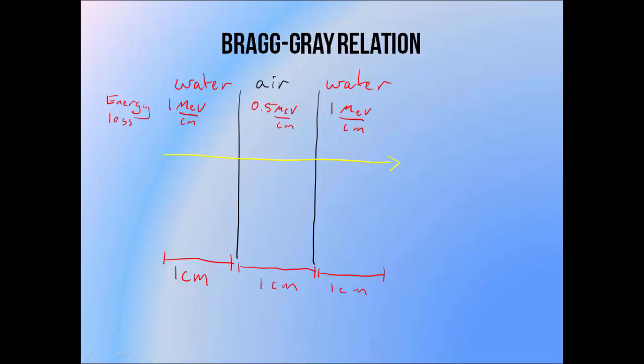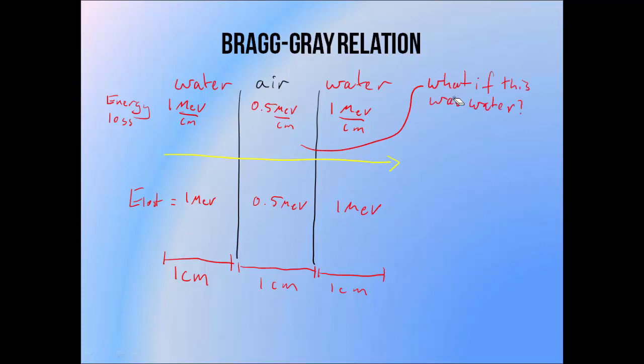An electron that travels 1 centimetre through the water above the chamber, and loses energy at a rate of 1 MeV per centimetre, will lose 1 MeV. An electron travelling 1 centimetre through the chamber, that loses energy at a rate of 0.5 MeV per centimetre, will lose 0.5 MeV. And it will lose another MeV in the water on the other side of the chamber. The Bragg-Gray theory uses this information to answer the question: what if the region of air inside the ion chamber was made of water instead? Well, we know the rate of energy lost per centimetre in water is 1 MeV per centimetre, so the electron would lose twice as much energy as it travelled that centimetre through the ion chamber. And the amount of energy deposited would be 1 MeV instead of 0.5 MeV. This is essentially all the Bragg-Gray theory does.